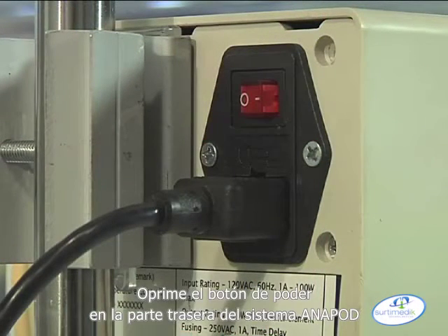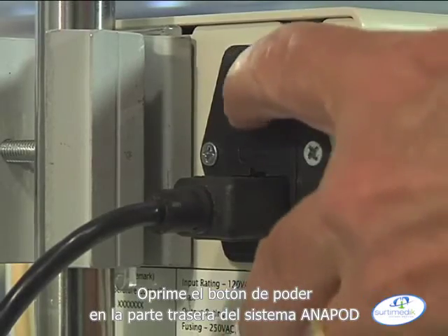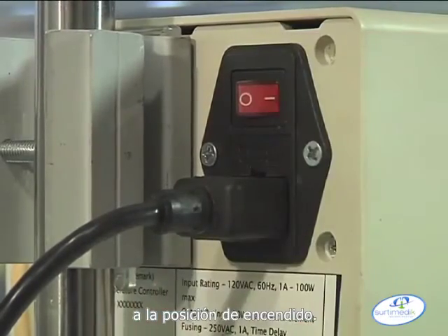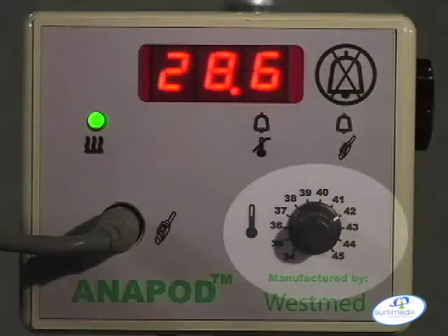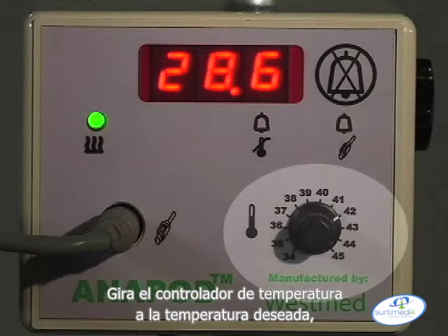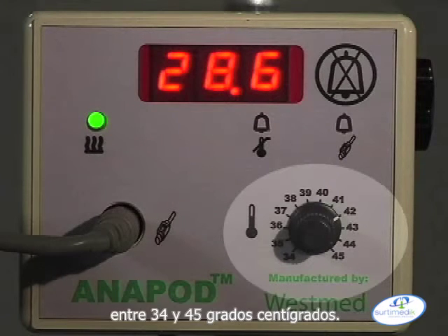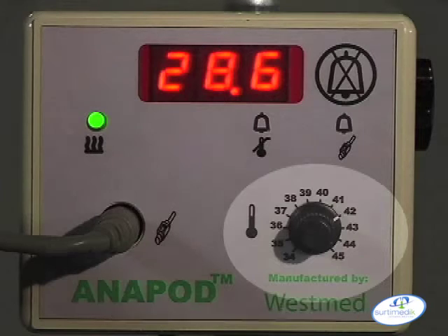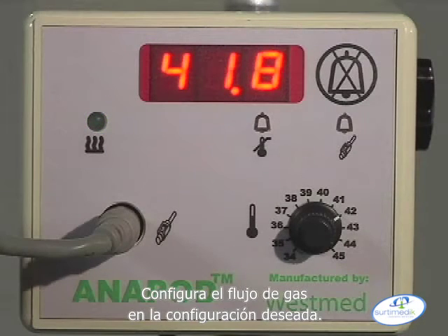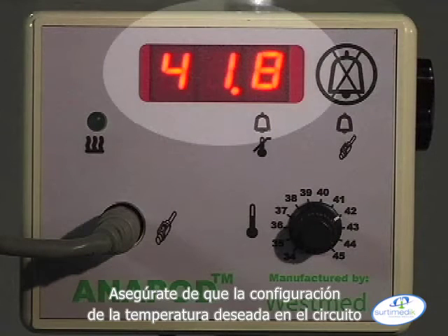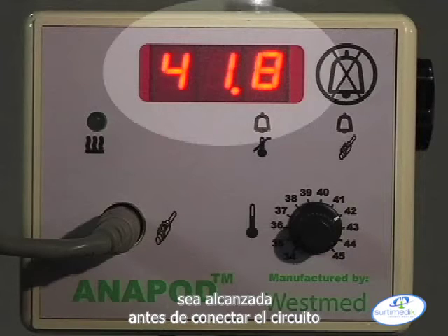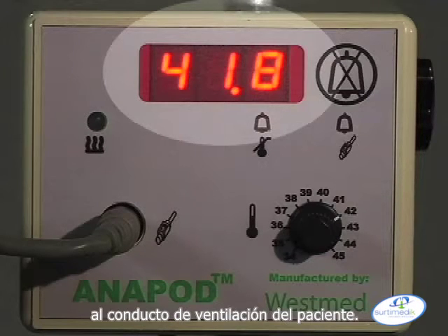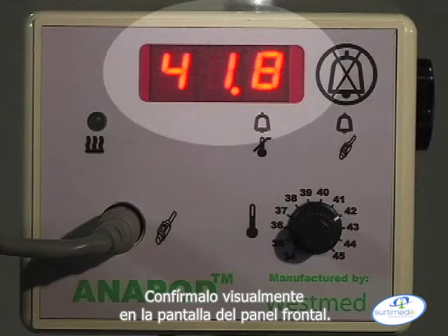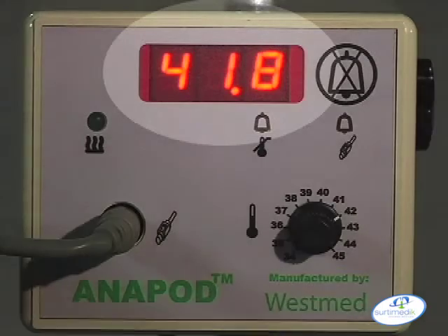Turn the on-off control switch on the rear of the Anapod humidification system to the on position. Set the temperature control to the desired temperature between 34 and 45 degrees centigrade. Set the gas flow to desired settings. Ensure the desired temperature setting in the heated wick circuit is reached before connecting the circuit to the patient airway. Confirm visually on the front panel display.